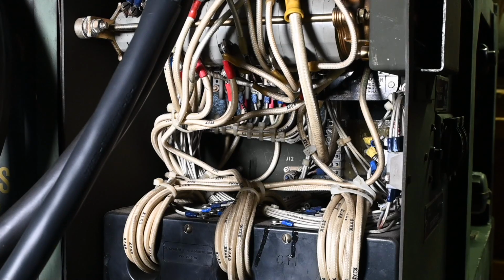It's marked as CVT1. In the tech manuals, it's referred to as a current voltage transformer. It's a little bit of an incorrect description. I've not actually seen such a device called that before, because you think, what is a current voltage transformer? Well, it's actually a magnetic amplifier. It's also known as a mag amp, and sometimes it's known as a saturable core reactor. And it's a very unusual device. You don't see them much anymore. Pretty much an old type of technology. And it's really key to how the voltage regulation works on this generator set.